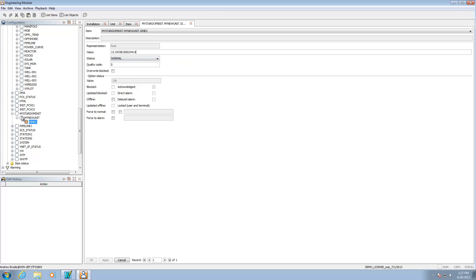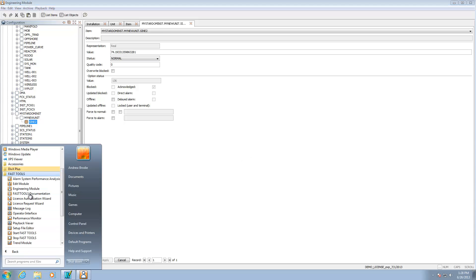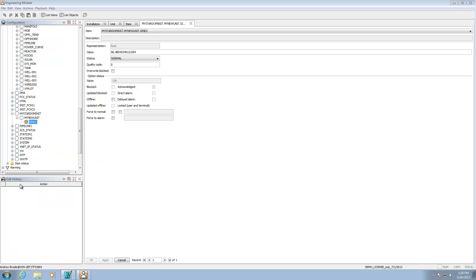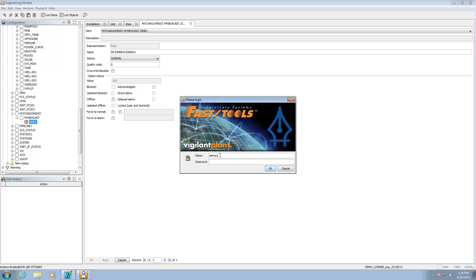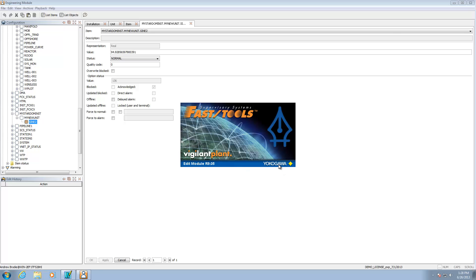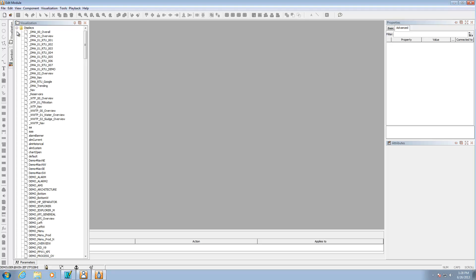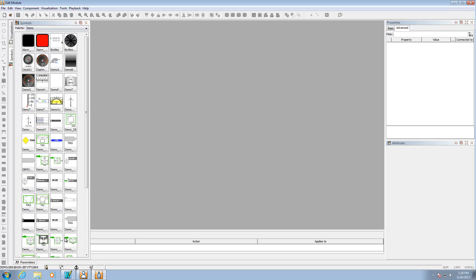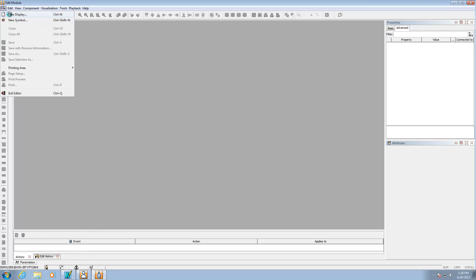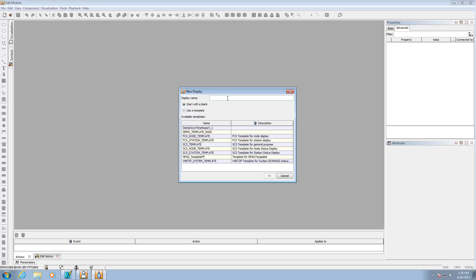Now that we have this real value updating inside FastTools, the next step is to add it to a screen. Go to Programs, FastTools, and the Edit module - this is where you add variables and create screens. After entering your username for security, go to Visualizations where existing screens are, and Symbols where pre-built widgets are available. Go to File, New Display, and give it a display name - I'll call it Stardom Demo Point - and click OK. Now I have a blank screen ready.